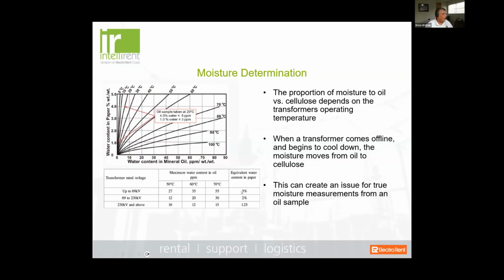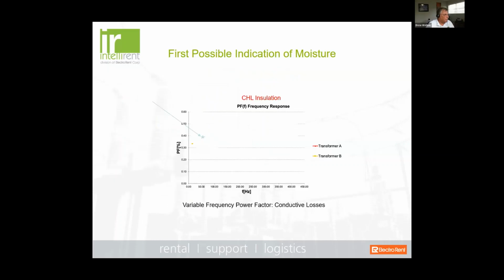Okay, so you'll see that in most extreme cases, 3% moisture content should be your maximum. Now we're talking about mineral oil. We're not talking about FR3 or any of the synthetics because they do have a much higher absorption rate. And this is something that the industry has not quite yet developed standards for. But if you talk to people from Cargill and other people that make synthetics, they will tell you that the withstand capability is much greater in terms of a ppm measurement on FR3.